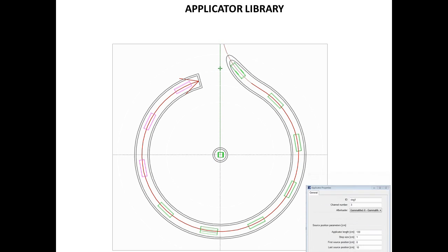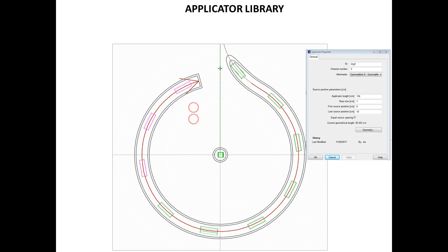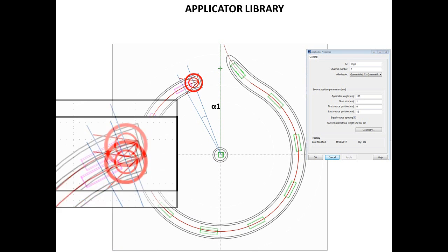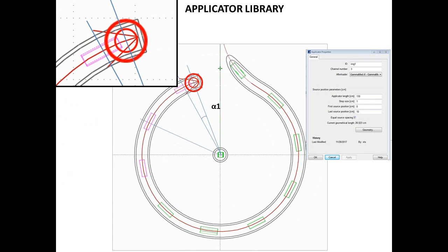For the ring applicator taken from the BrachyVision applicator library, we measure the source angular steps curve by using the same method. In this case, the angular zero coordinate we define at the center of the circle, which is delineated inside or outside on the applicator tube tip. From this zero starting angle, we measure angular source position number 1, source angular position number 2, and so on.